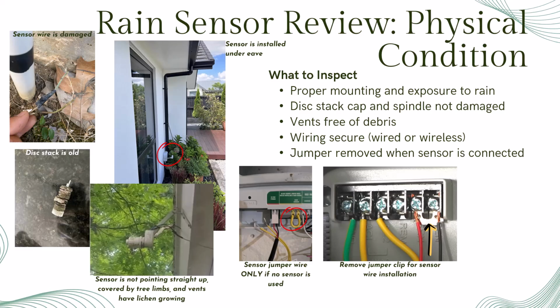For wired sensors, I look over the cable for cracks or exposed wiring. At the controller, I confirm the wires are attached securely to the sensor terminals or, on older systems, tied into the common. If it's a wireless unit, I check that the receiver wiring is clean and secure. One last detail. If a sensor is wired in, the jumper must be removed or the controller will ignore the sensor completely.